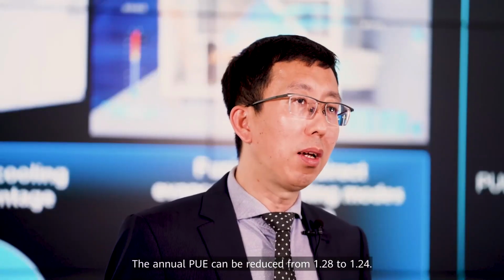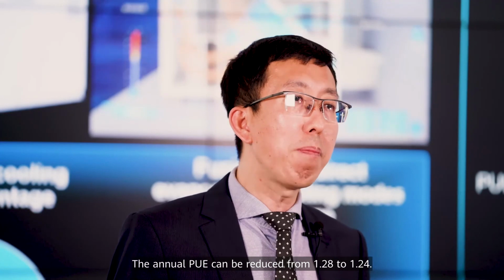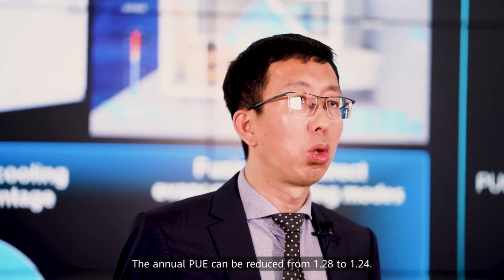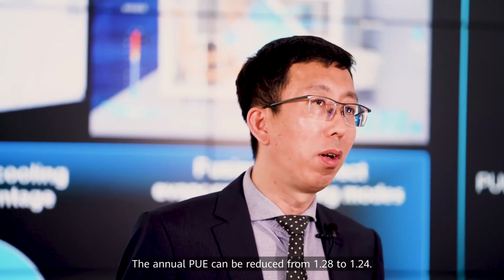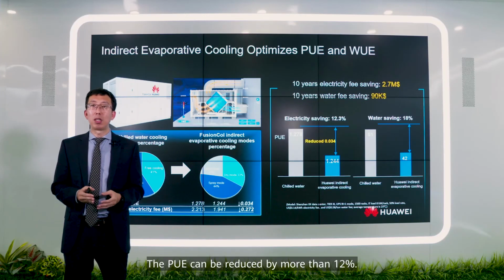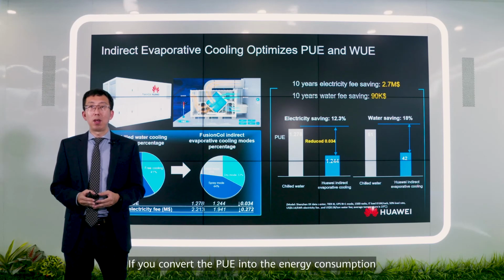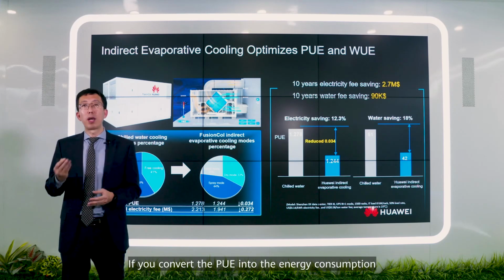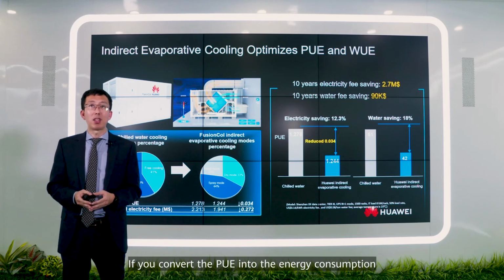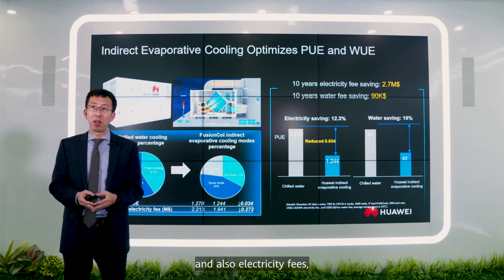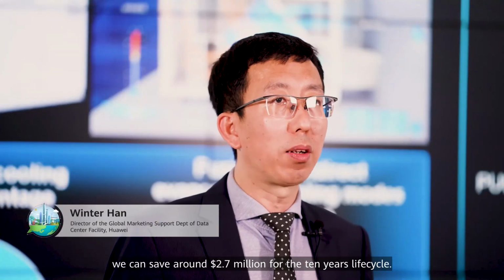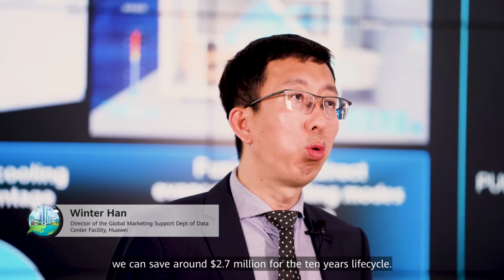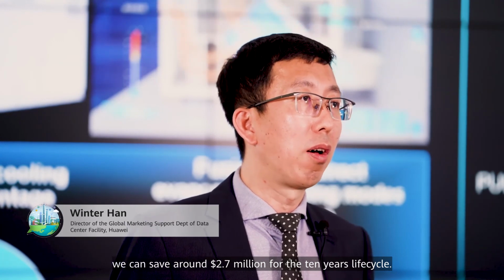The annual PUE can be reduced from 1.28 to 1.24, a reduction of more than 12%. If you convert the PUE into energy consumption and electricity fees, we can save around $2.7 million over a 10-year life cycle.